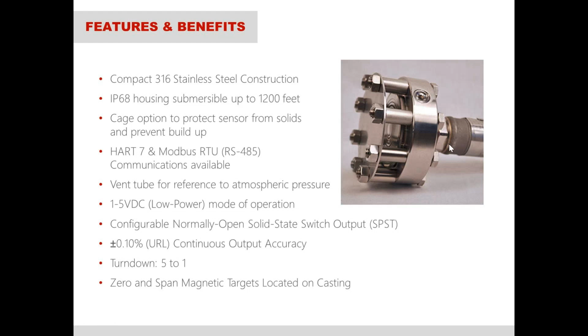Now, if you need a lower range than what our lowest range is, I believe with our turndown, the lowest range that we offer is a 0 to 7 feet of water column. That's with a 0.1% accuracy. If you need to go lower than that, there's nothing stopping you in the software from going past the 5 to 1 turndown if you need to. And you can always do it in the software of their PLC or their DCS system as well.